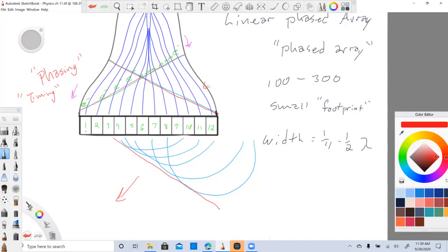So I'm sorry, I didn't read this prior. I'm pretty sure, and correct me if I'm wrong if you're reading through, in the linear phased arrays, every time a beam is created, all the elements are used. I'm just not seeing that anywhere, so I'm a little afraid I'm saying that wrong, but more about linear phase. All the active elements, yeah, so all of the elements are used every time. So every beam of sound is created by all the elements. That actually is the key to why it's a pointy top.